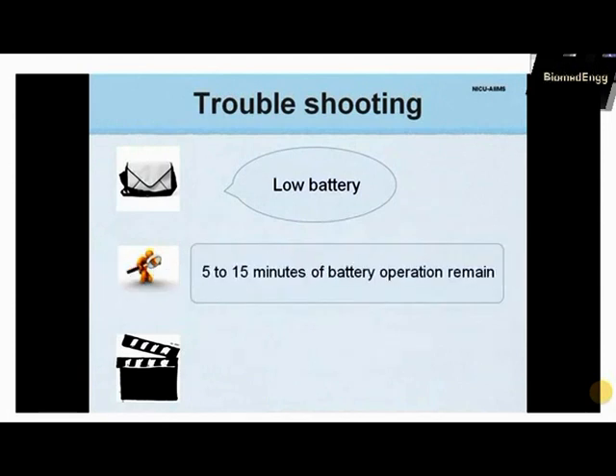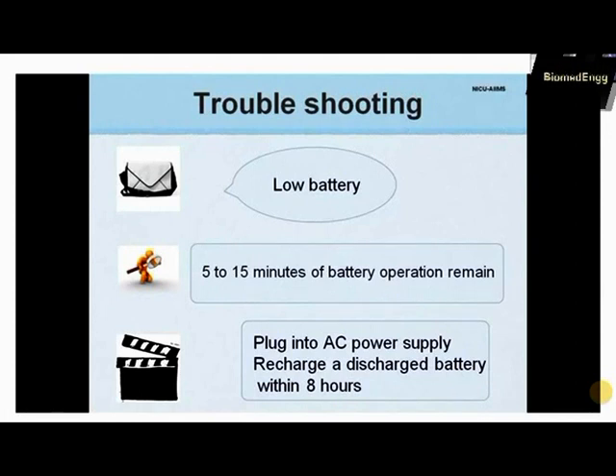A low battery message indicates only 5 to 15 minutes of remaining battery power. Plug the oximeter into AC power supply, and to prevent permanent damage to the battery, recharge a discharged battery within 8 hours after a low battery message is displayed.